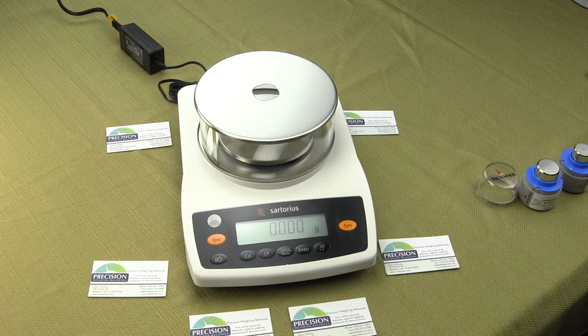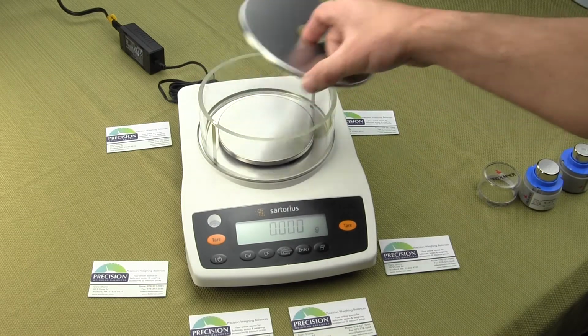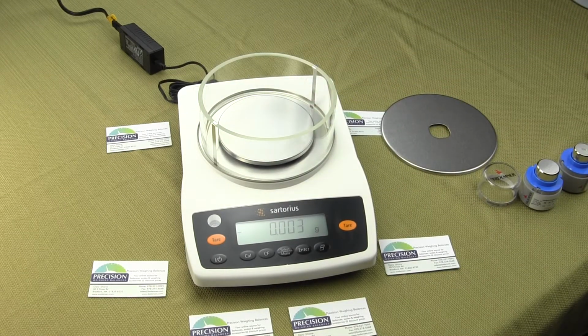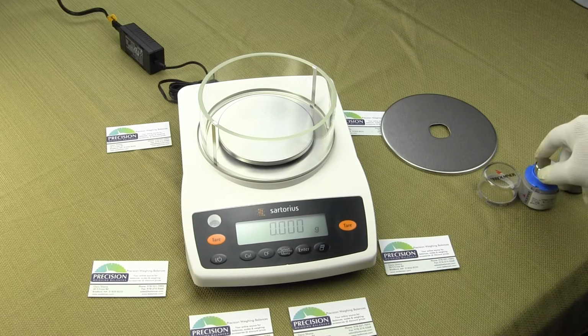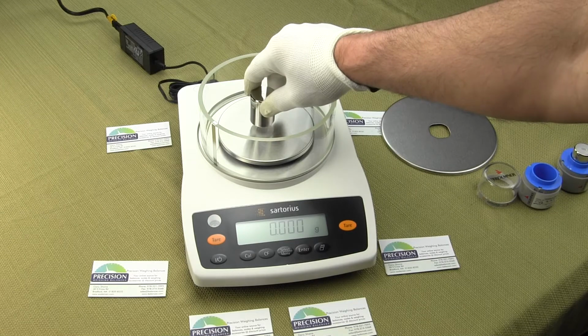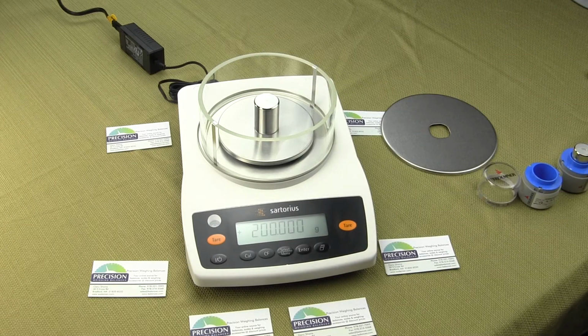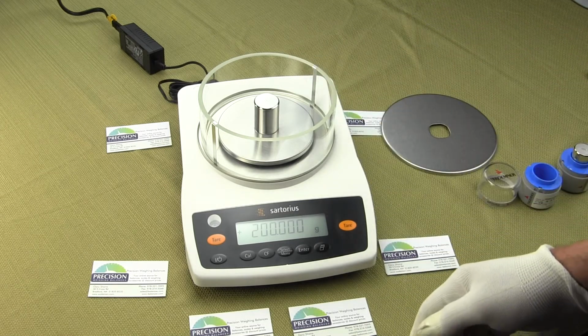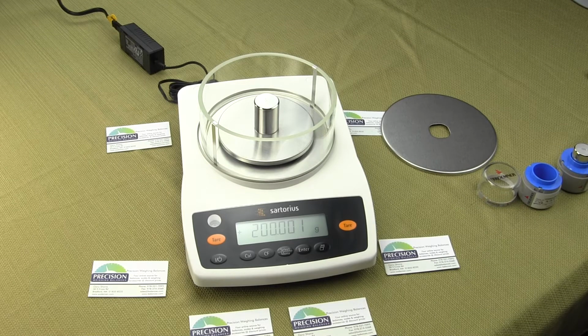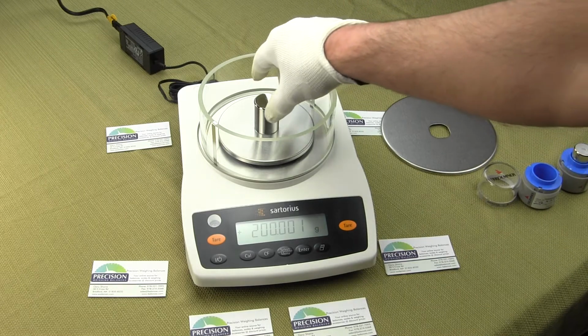So I'd like to show you the performance of this balance. You'll notice it has a very quick response time. I have a few calibration weights. So we have a 200 gram, and we do sell these Tromner weights. And you can get an idea on the response time. You'll see how quick the balance is. You notice the balance isn't drifting. That's because this is a force restoration balance. So in Sartorius' series, they do have the Entris 153, which is a strain gauge, but the remainder of the models, the Sartorius 323S, 423S, and 623S, these are all force restoration balances.